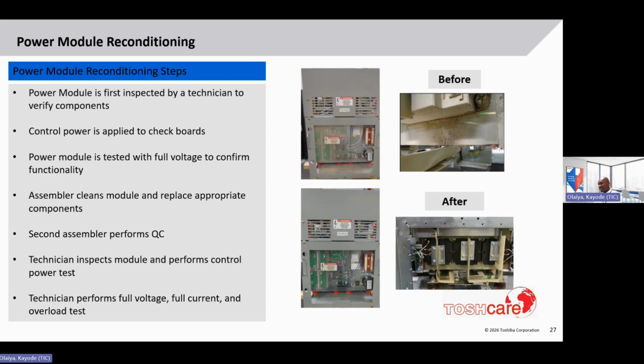And then finally, the module will be tested with full voltage first. So no load, but full voltage, making sure that all the signals are good and that the power devices are functional. And then it's going to be full current test so that we know that the module can handle the rated FLA. And then finally, an overload test. Make sure that the module can handle an overload condition without damage. And so after all of this is done, we know that this module will work in the field and the customer can have confidence in what we've done.